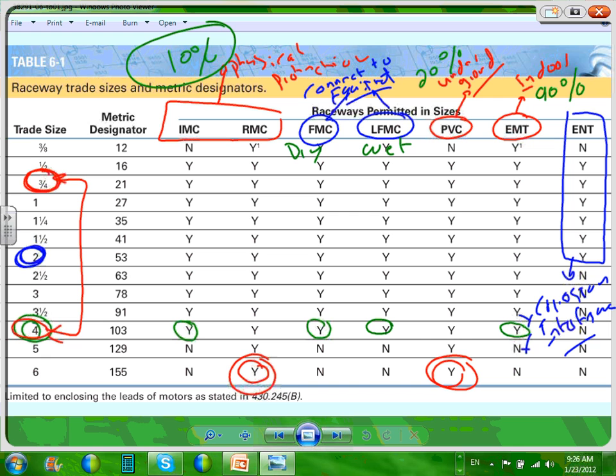Any question, guys, about these conduits? Yes, sir. These look, guys, you'll see a picture of them, like flexible metallic conduit, but non-metallic. They are flexible. We can't buy them in pieces, but they're flexible ones. Pushing conductors through them is a nightmare. Pushing conductors through any flexible conduit is a nightmare, unless it's 6 foot fixture whip.